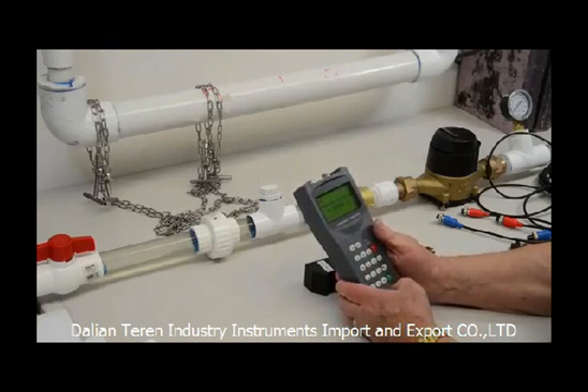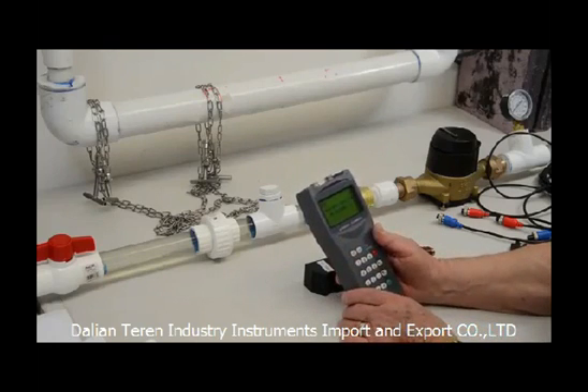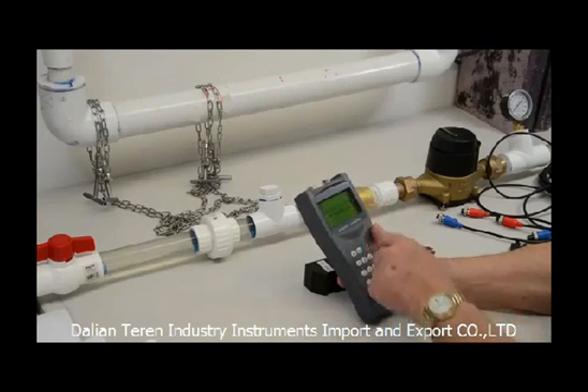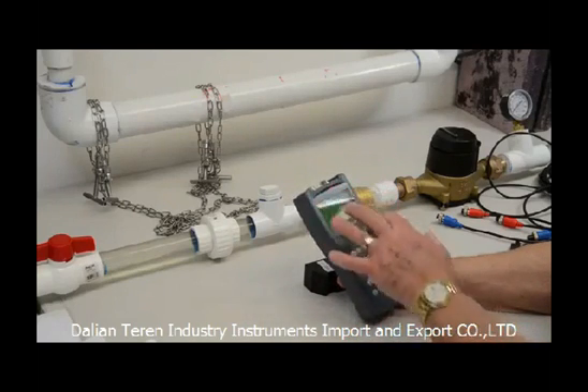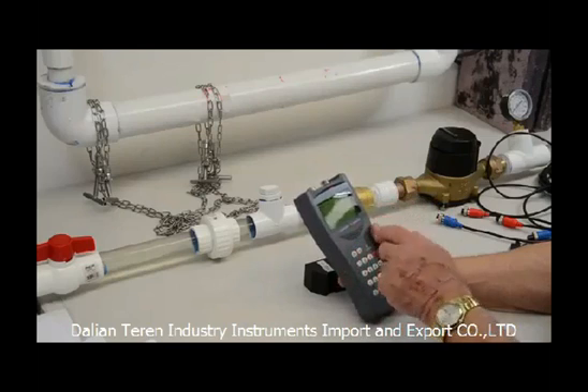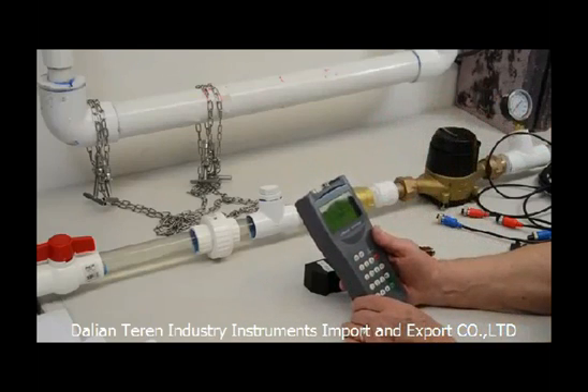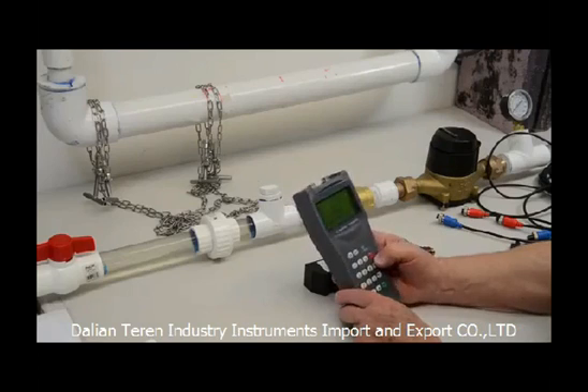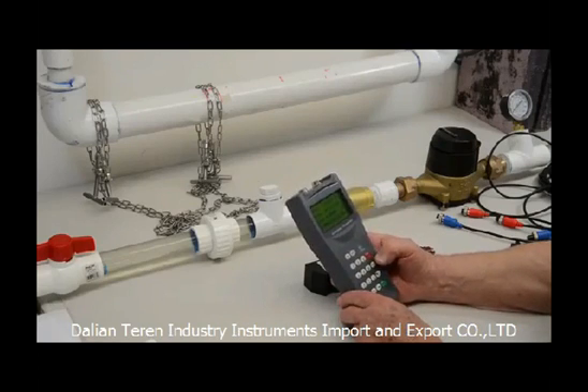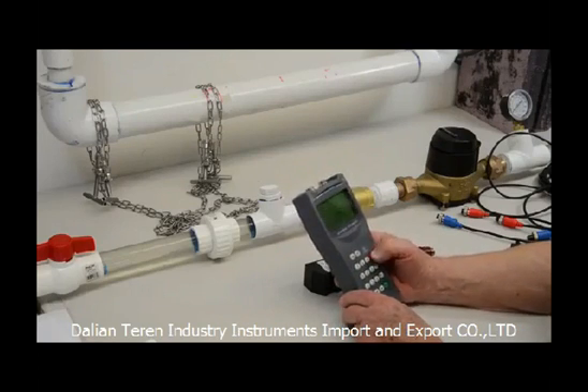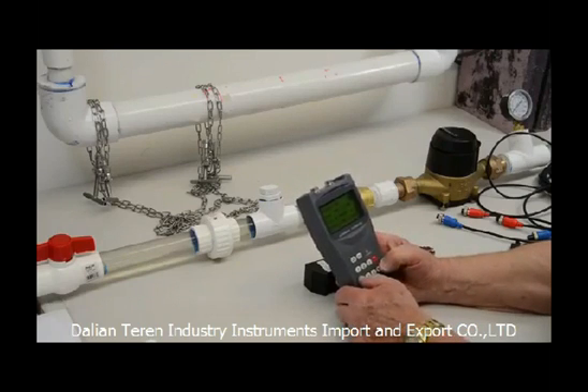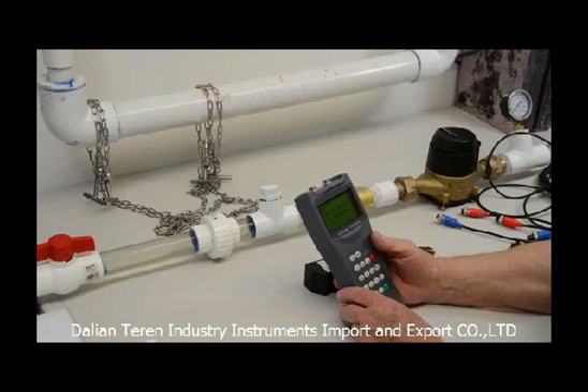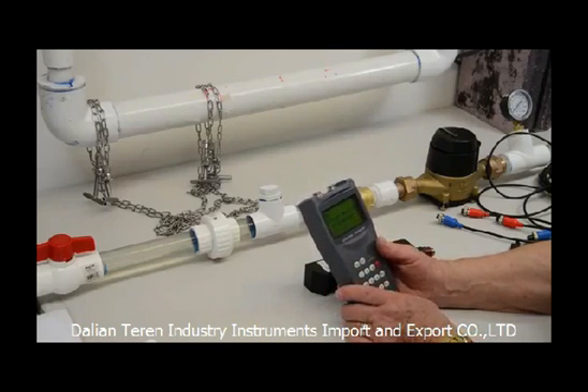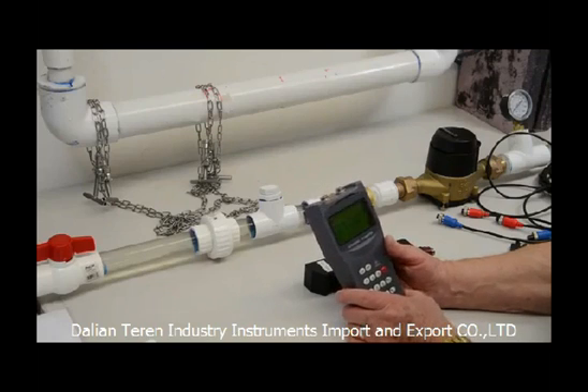The next step I do is to do my transducer spacing, menu 2-5. My spacing is 0.912 inches. The flow meter has calculated what my spacer is based on the data that I put in. The next step I'm going to go to is my transducer mounting, and there's several issues here. Menu 2-4, and this is the mounting that I'm going to select and how I'm going to do it. In this case, I'm going to use the V method, which is my transducers in line.